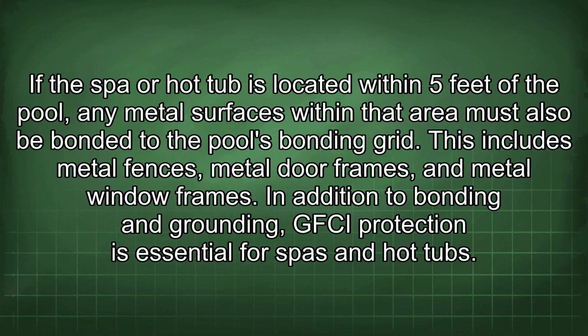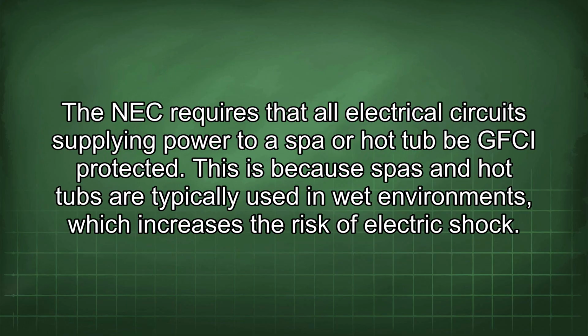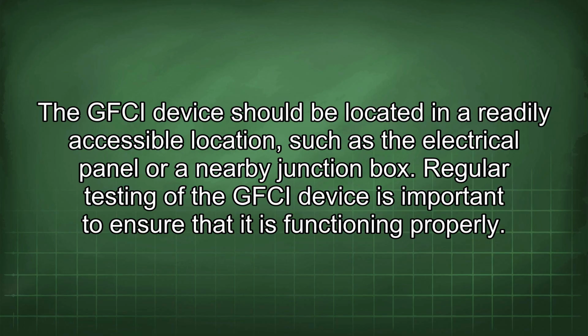In addition to bonding and grounding, GFCI protection is essential for spas and hot tubs. The NEC requires that all electrical circuits supplying power to a spa or hot tub be GFCI protected. This is because spas and hot tubs are typically used in wet environments, which increases the risk of electric shock. The GFCI device should be located in a readily accessible location such as the electrical panel or a nearby junction box. Regular testing of the GFCI device is important to ensure that it is functioning properly.